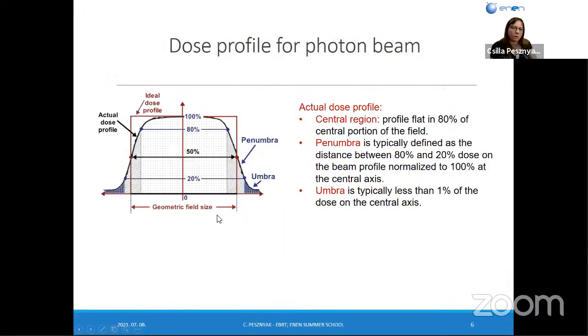After that, it's also very important, and we also have to measure the dose profile for the photon beam and also for the electron beam, but there are no larger differences. I'm going to show you only the photon beam. This is the central region, this part. It is a profile flat in 80% of the central portion of the field. This is at 80%, and everything under this section is the central region. We can find the penumbra. It's typically defined as the distance between the 80 and 20%. This is the penumbra side.